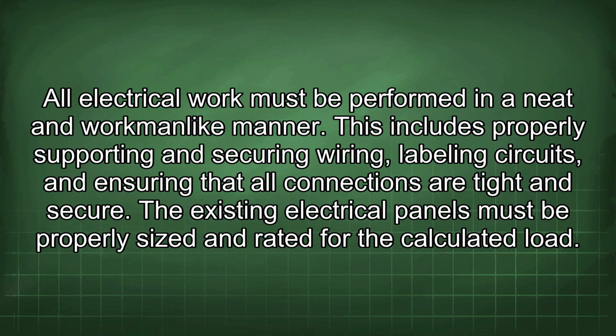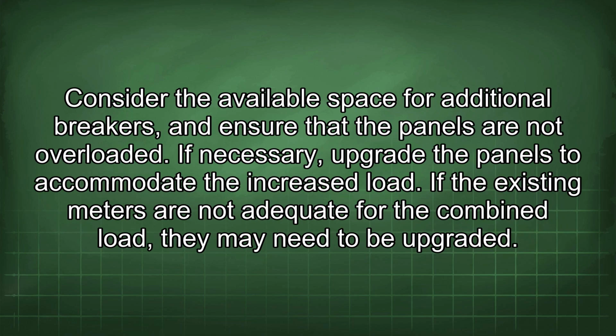All electrical work must be performed in a neat and workmanlike manner. This includes properly supporting and securing wiring, labeling circuits, and ensuring that all connections are tight and secure. The existing electrical panels must be properly sized and rated for the calculated load. Consider the available space for additional breakers and ensure that the panels are not overloaded. If necessary, upgrade the panels to accommodate the increased load.